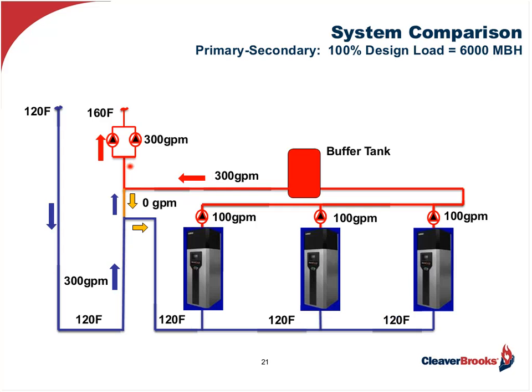That means we're going to get 120 degrees back to the boilers, and that's good. They're getting cold water. And the boilers, because they're matched to the load, are all going to be at 100% firing rate. Now, one point I'd like to make, this is an idealized system. In 35 years of designing boiler rooms and boiler systems, I've never seen the boilers perfectly match the load. The more the boilers are oversized, the worse the results are going to be.